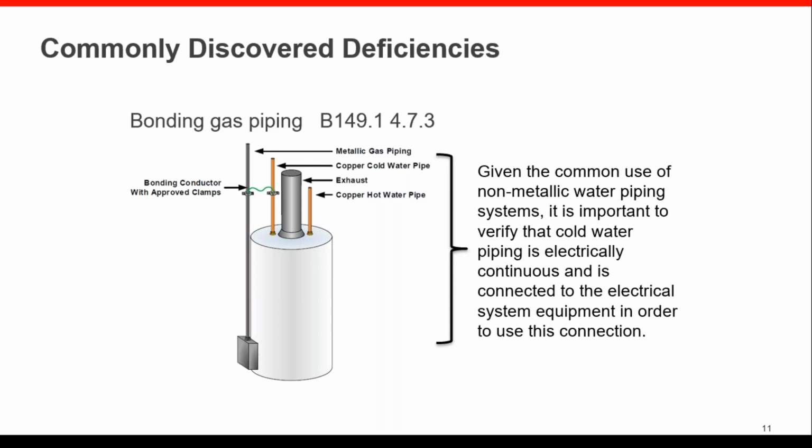So the thing you need to be aware of is that if people are making repairs or using some of the newer insulated fittings or the plastic fittings that may disrupt the continuity, and you run into that kind of a situation, then you're going to have to put some kind of a bonding jumper wire around that. But please be cautious, just don't assume that piping is continuous all the way back to a good solid ground.